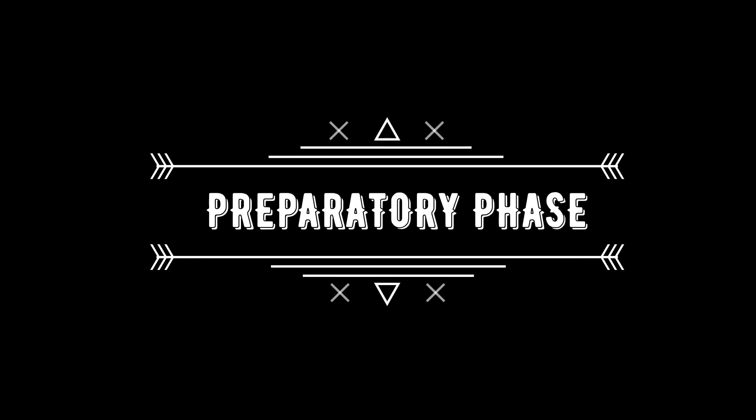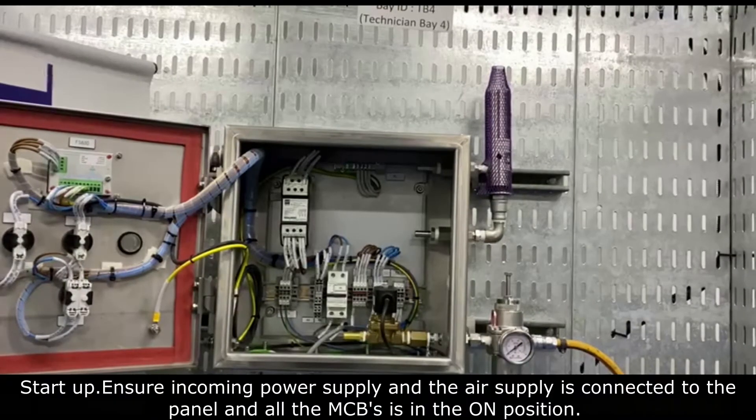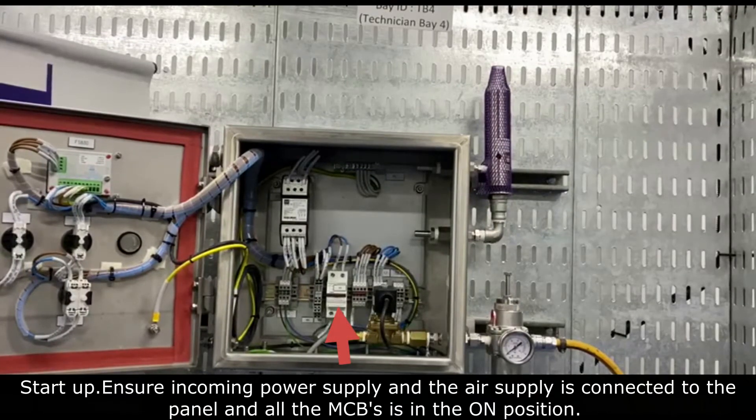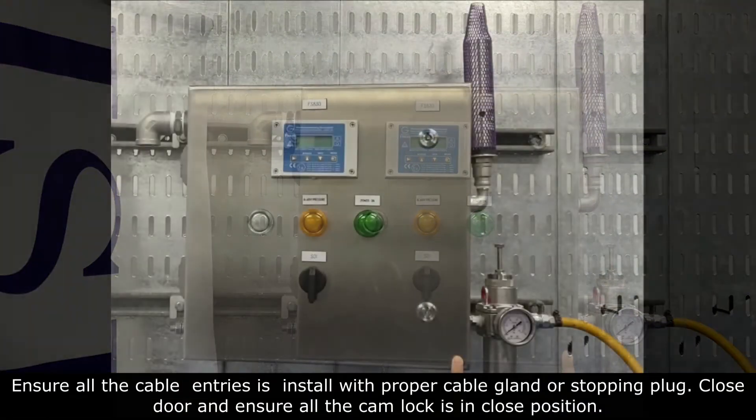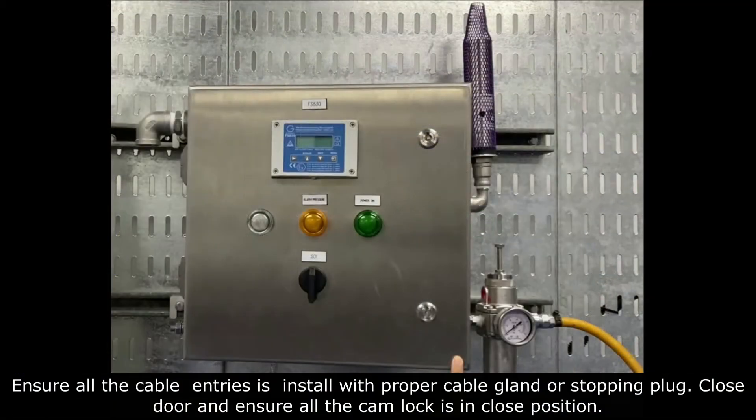Preparatory Phase. For startup, we need to ensure all incoming power supply and the air supply is connected to the panel and all the MCB's are in the on position. Then we need to ensure all the cable entries are installed with proper cable gland or stopping plug. Close the door and ensure all the cam locks are in the closed position.